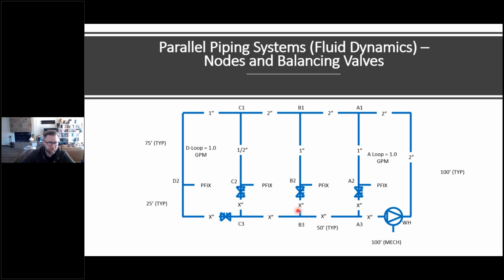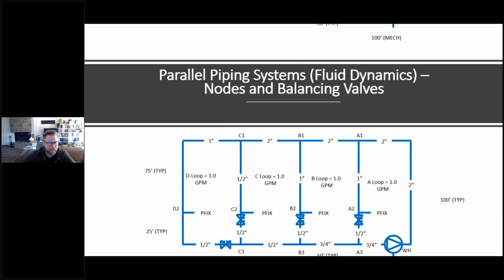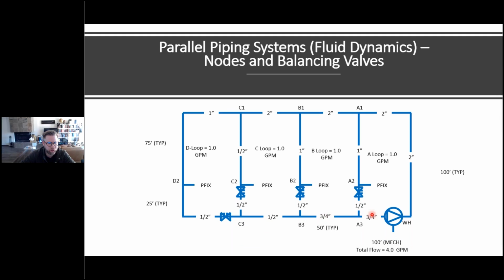I think we could be pretty confident that each of the individual loops that only saw 1 GPM could be a ½ inch pipe for that GPM. And then at this segment where we had 2 GPM, we could still say a ½ inch. And then as we increase to 3 GPM, we may want to increase to 3/4 inch, and 4 GPM would still be a 3/4 inch. So we'd see this progression that would look something like this, where it's a ½ inch, and then increasing to 3/4 inch as we go through. So you have to start off, but keep in mind when you make that assumption for the pipe size on that first go around, it's your first guess at that hot water return pipe size.